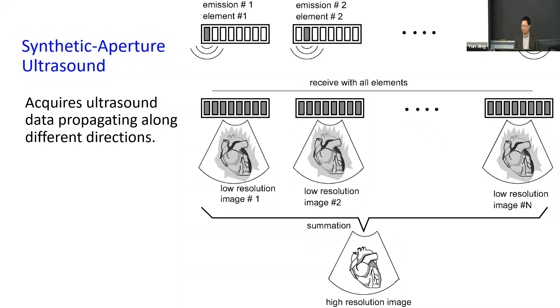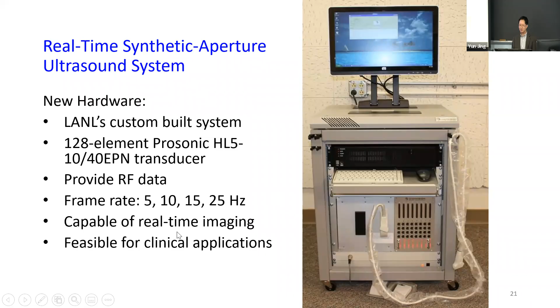So at that time, when we started research, there was no synthetic aperture ultrasound equipment available. So we basically custom built this machine, and it can do real-time synthetic aperture ultrasound data acquisition. In total it has 128 elements and provides radio frequency data, the raw data we can use to do the imaging. The frame rate can be up to 25 Hertz. That allows real-time data acquisition for patient studies, because for patient studies we need real-time data acquisition. And that's why we're capable of real-time imaging, and that is feasible for clinical application.